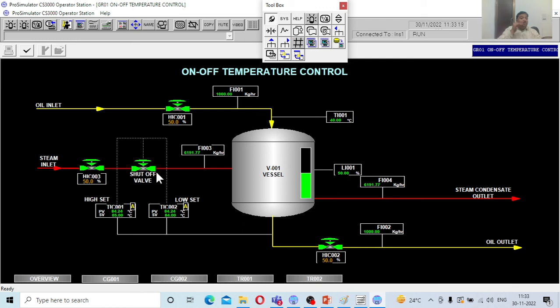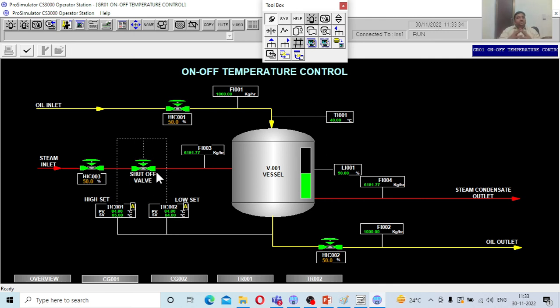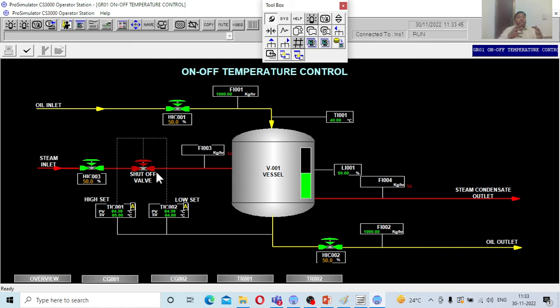In a real plant, increasing the on-off frequency would cause high wear and tear on the valve, damaging it very soon. That is why when using on-off control, make sure the boundaries between high and low set points are set sufficiently wide. I hope you have learned about on-off temperature control. We will meet again with other controllers. Thank you — Dr. Sudendra signing off.